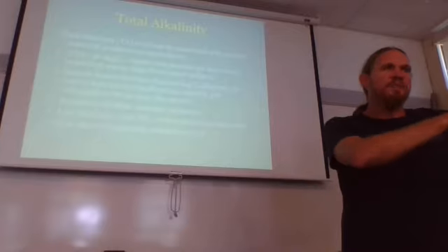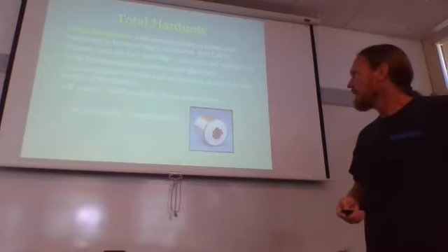Having alkalinity below 40 or 50 milligrams per liter, you basically have no biofiltration capacity at all because there's not enough carbon source for the bacteria to do their job. And as you'll see in a minute, if you remove carbonate ions, it's going to reduce the number of bicarbonate ions, always. You'll see why in a second.